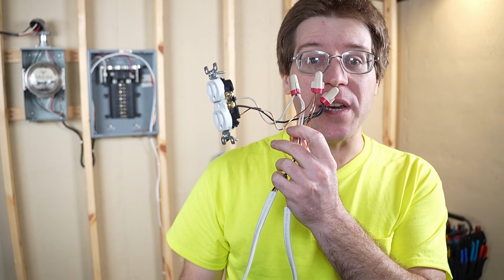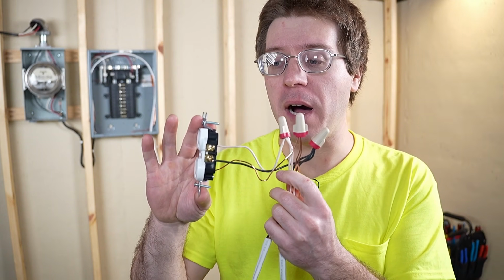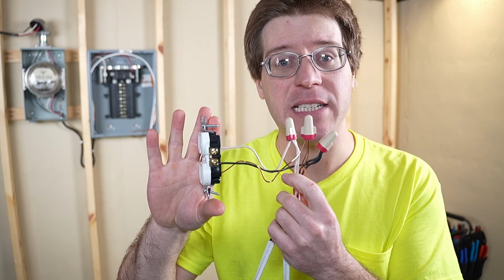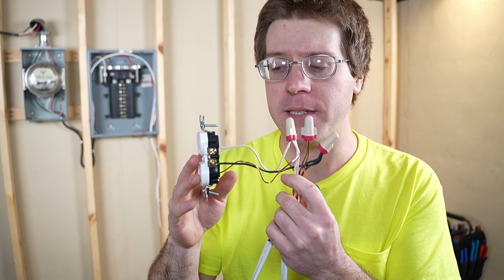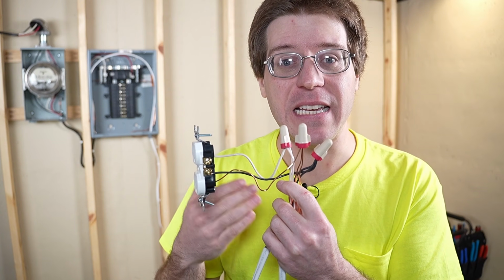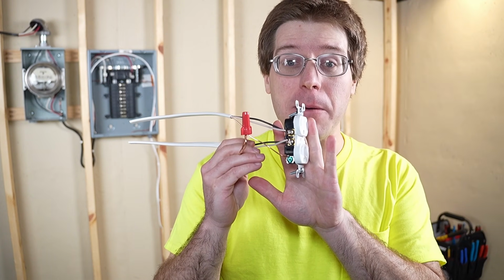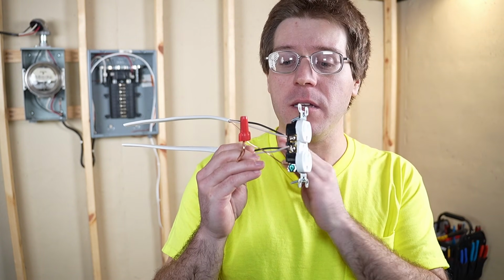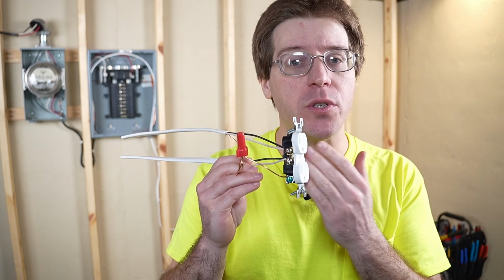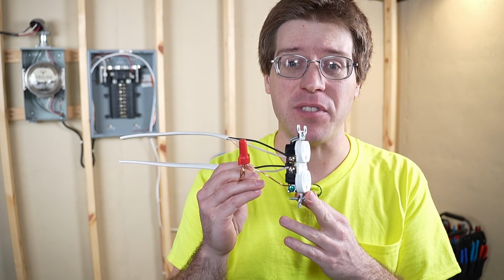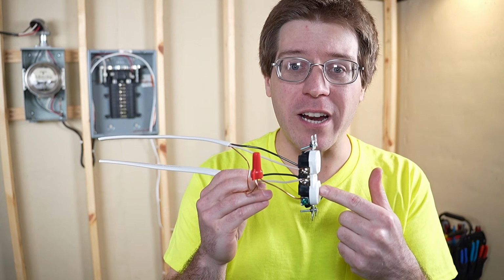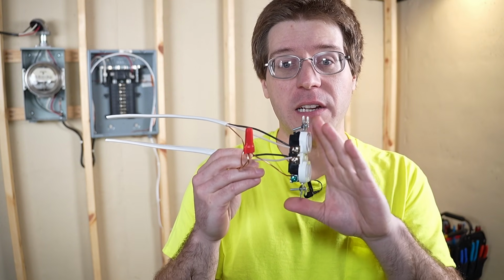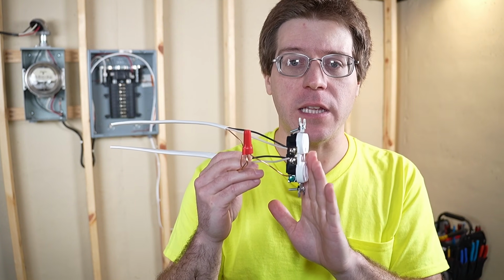My preferred method is the pigtail method. In my personal opinion, it seems more robust. It's not relying on the device itself as a splice point, and it can make troubleshooting a lot easier. I absolutely see the appeal to using the terminal method though. It's 2 less wire nuts, 2 less pigtails, and it actually saves a little bit of time. You're stripping out the wire anyway, but you're just looping it and installing it on the receptacle. I definitely get the appeal to this.